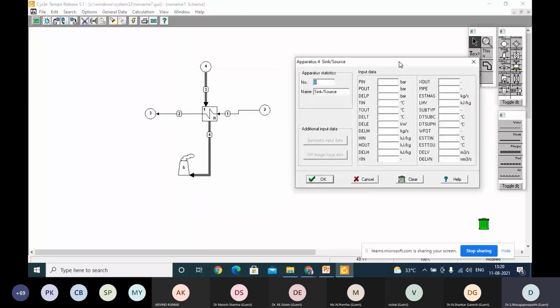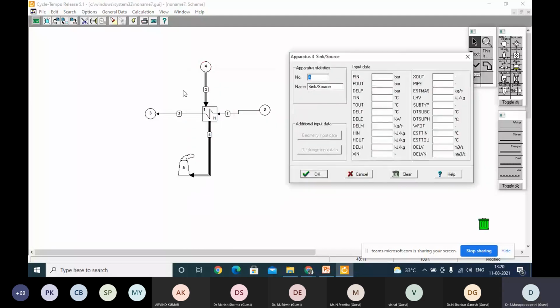Apparatus 4 is nothing but the flue gas coming out. At what pressure does it come out? It's 1.013 bar, and the temperature is around 270 degrees Celsius, and del M at which it is leaving is minus some 130 kg per second.